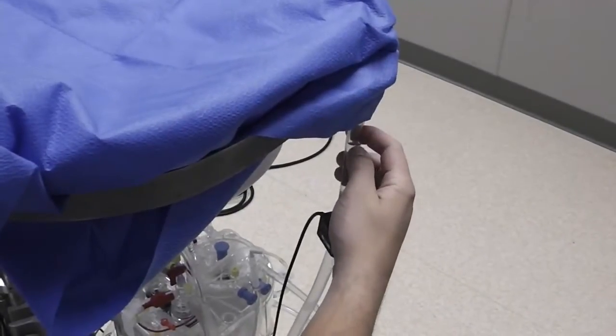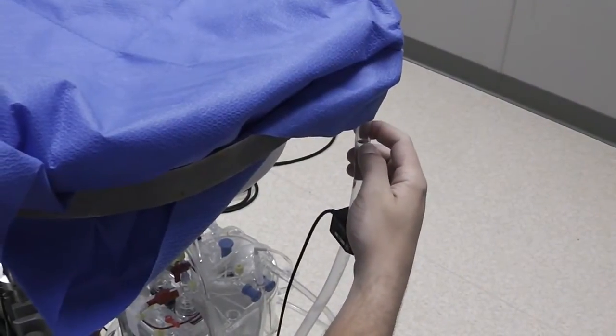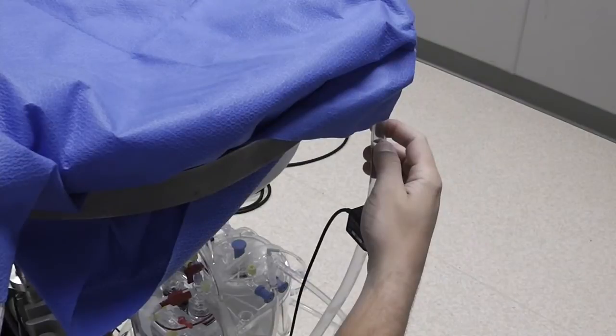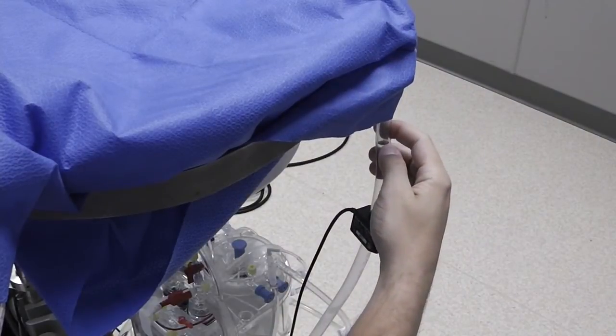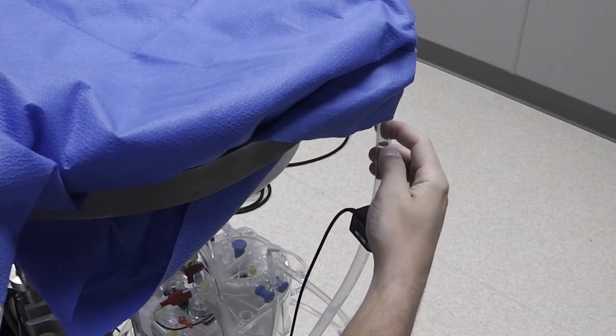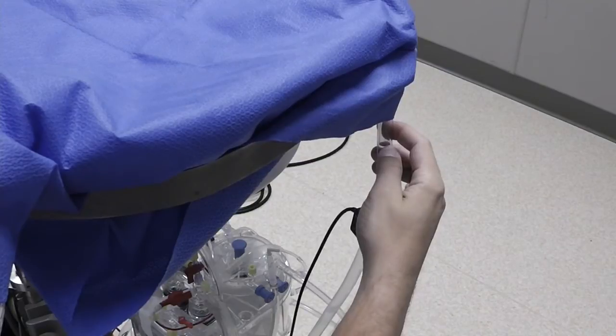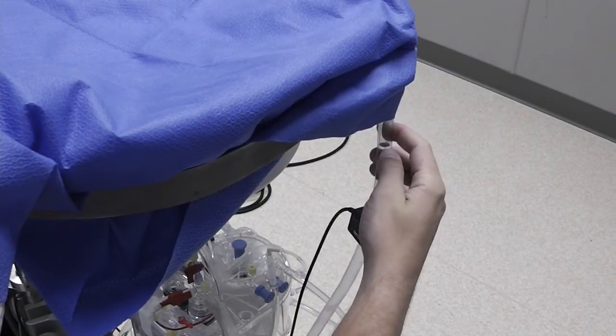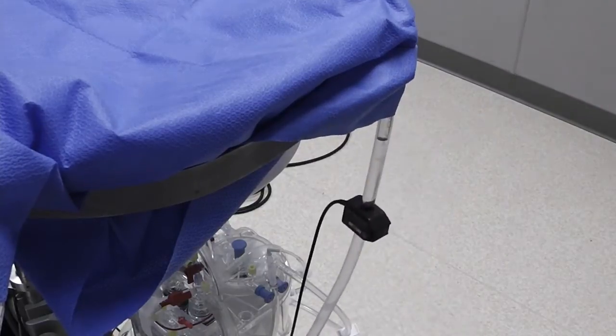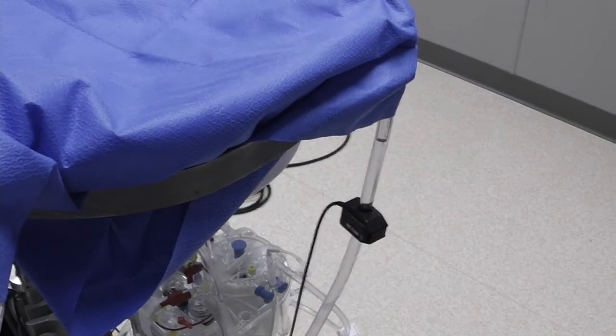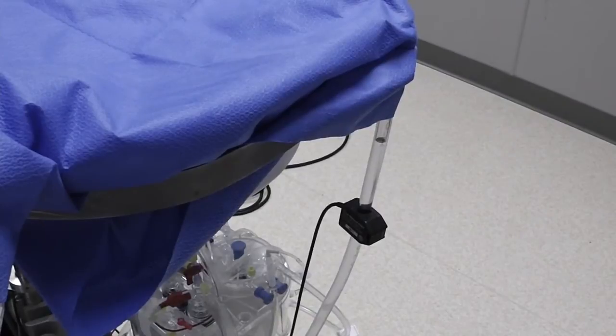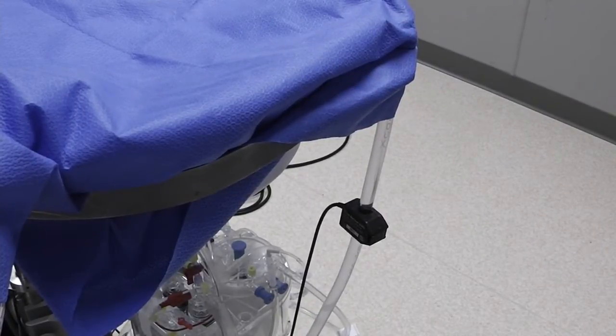So you can see where we're at here. Still getting more of a drop than I'd like. I'm going to occlude that a little bit more, and we're going to adjust this until we get that proper occlusion. That looks good. Once that's set, we're going to open the pump up to 4 liters a minute, something like that.